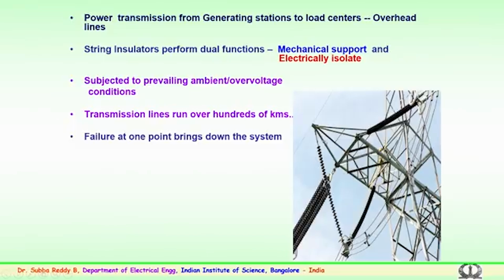One is to mechanically support the high voltage tower, and the second is to electrically isolate the conductor. These are the conductors, these are the different spacers. So, these have to be electrically isolated from the tower as the conductors are at very high voltages. So, in the transmission network, which exists as an outdoor system, these insulator strings are subjected to prevailing ambient and over voltage conditions.